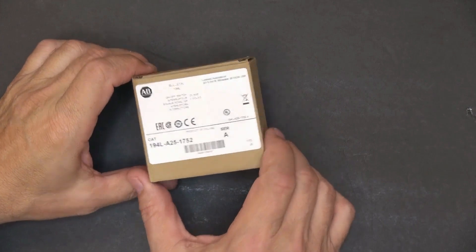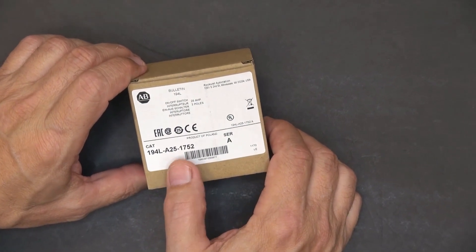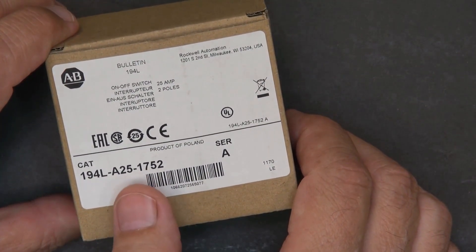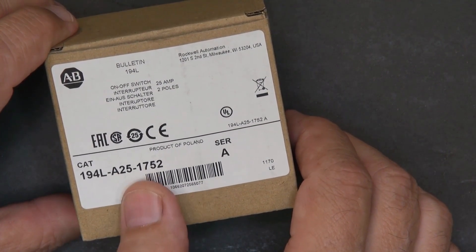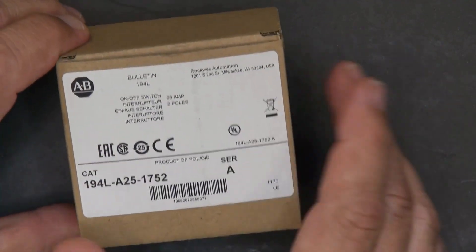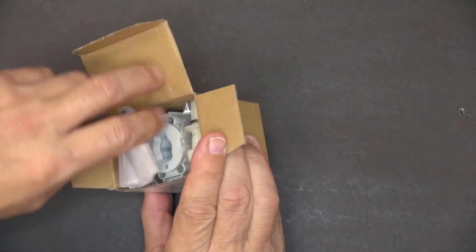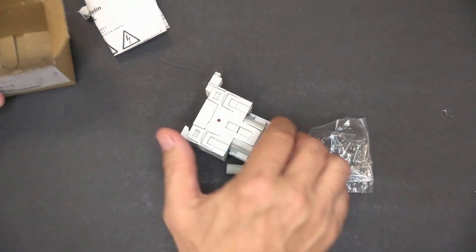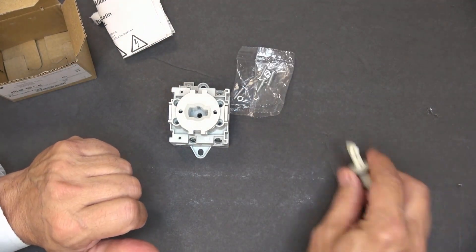Let's take a look at a switch right out of the box. This is a 194L-A25-A175-2 — a base mount switch where A indicates 25 amp, 175 is an on-off switch, and 2 indicates that it's a two-pole. Here's what it would look like within the carton. Let's open it up. Here's the instruction sheet. Here are the individual parts: the actual base mount switch, mounting hardware, and the shaft.